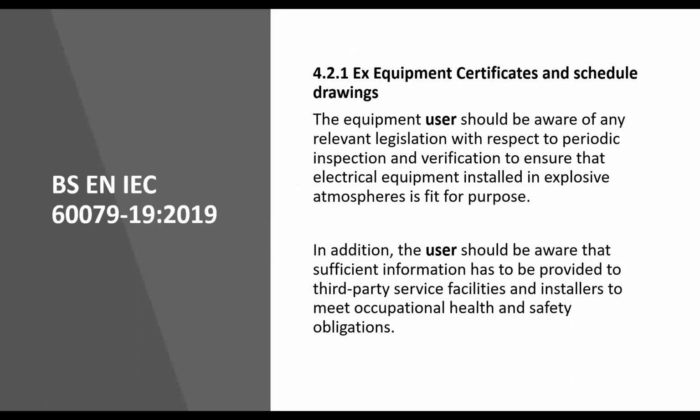Again, the equipment user should be aware of any relevant legislation in respect to periodic inspection and verification that electrical equipment installed in explosive atmospheres is fit for purpose. So making sure it is fit for purpose. That's the user's responsibility. How do you know it's fit for purpose if you haven't got the correct paperwork back? In addition, the user should be aware that sufficient information has to be provided to the third-party service facility, the repairer, and that information to installers to meet health and safety obligations. The user has a lot of responsibility.